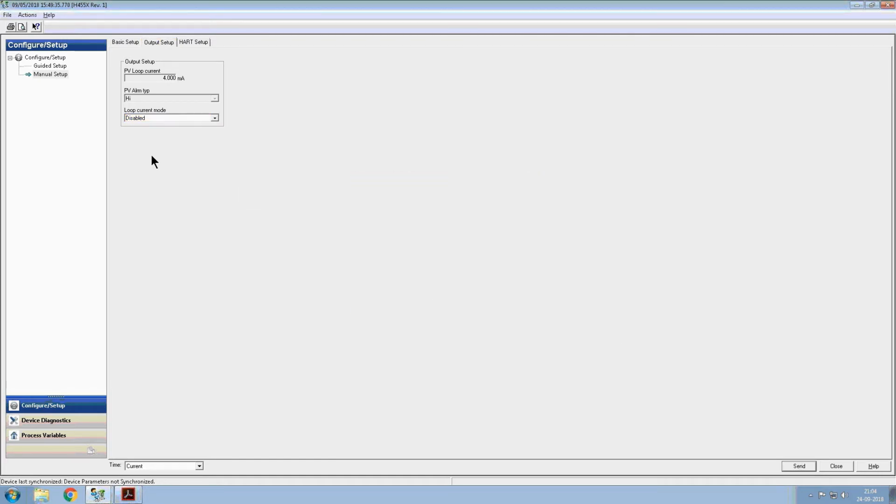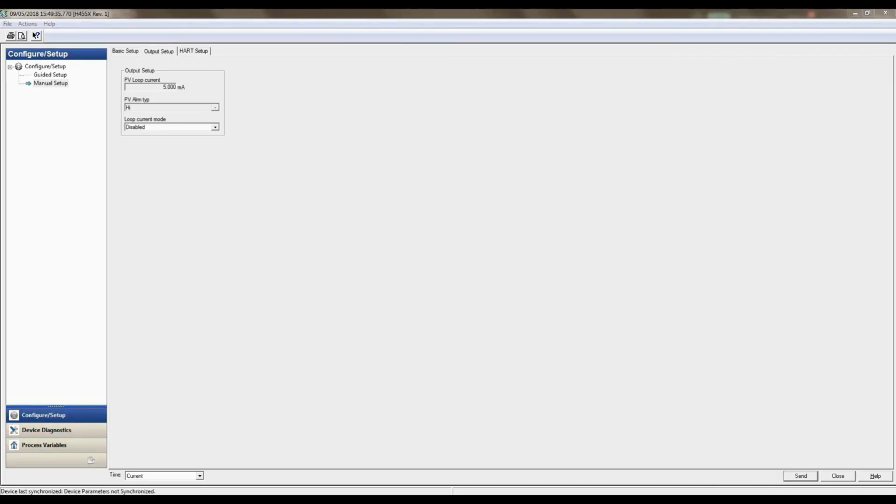It also disables the latching of analog output to 4 mA in case of a PV under range status and to 20 mA in case of a PV over range status. The self-diagnostic routine still remains active, thus continuing the alert reporting as per the PV measurement. Failure signals in multi-drop transmitters are communicated through the HART messages.